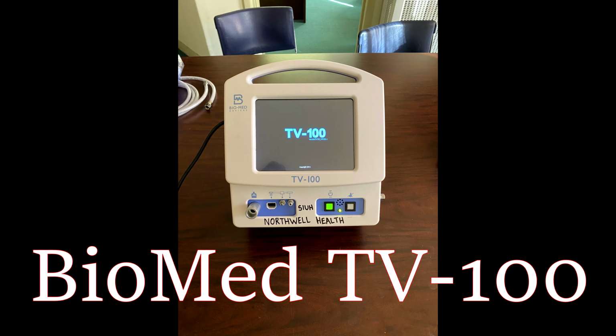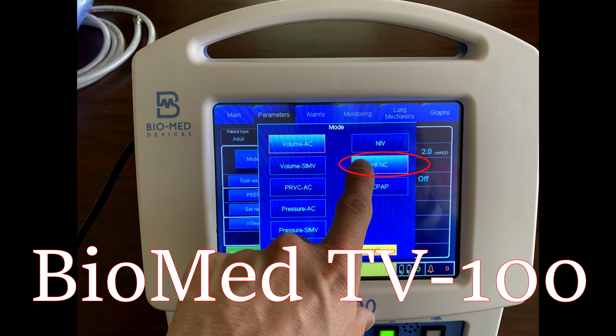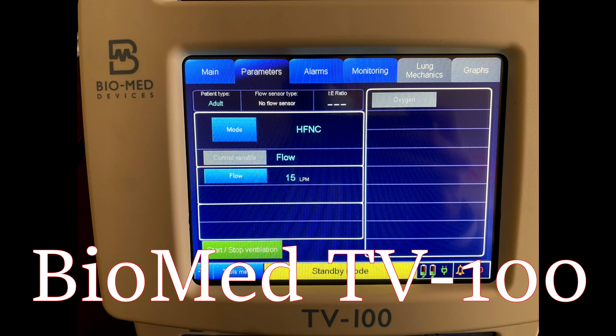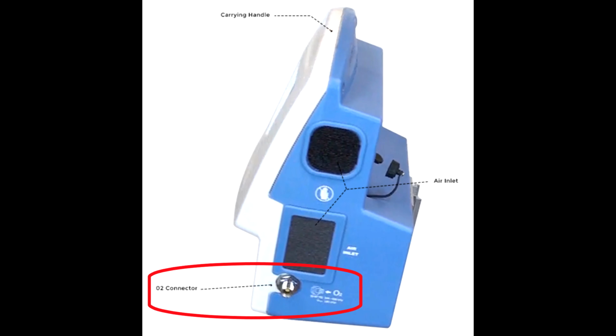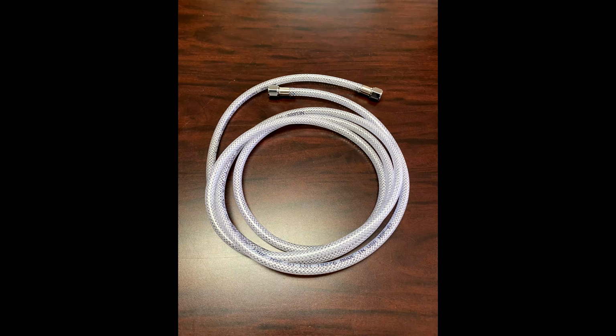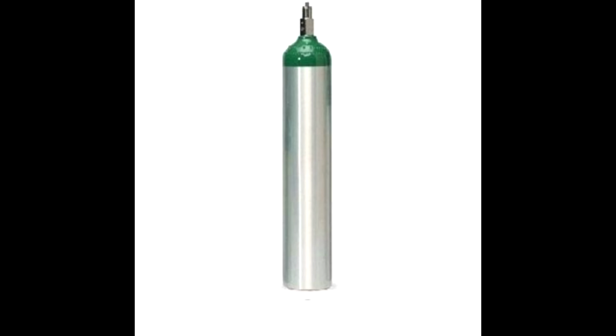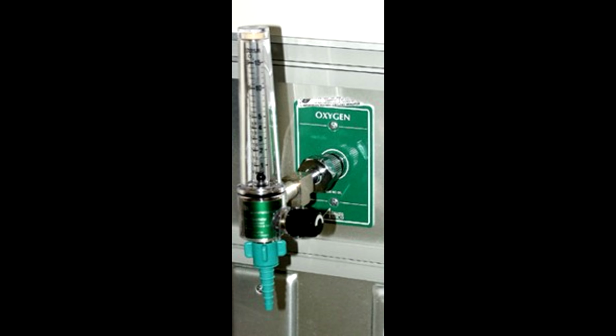In order to treat a patient using high-flow nasal cannula, we need a few things. To start, we need a ventilator with the high-flow nasal cannula mode. Our department now uses the TV100, which has this mode. On the side of the TV100 is an O2 inlet connector. Here you attach the 50 psi pressure oxygen tubing, and the other end attaches to either your oxygen tank or oxygen flow meter found on the wall at the hospital.